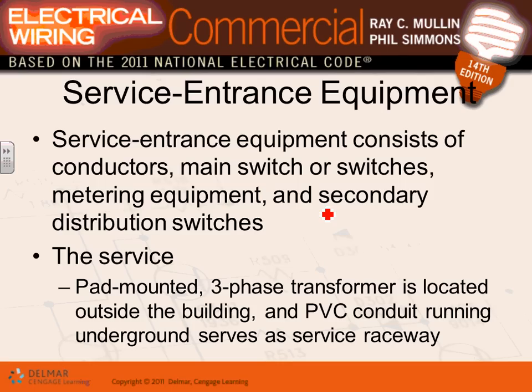Conductors, also service entrance. Now, the service entrance equipment, typically you have your conductors, your main switch or switches, metering compartment, all these are called service equipment. The service pad mounted three-phase, this is just for the building.